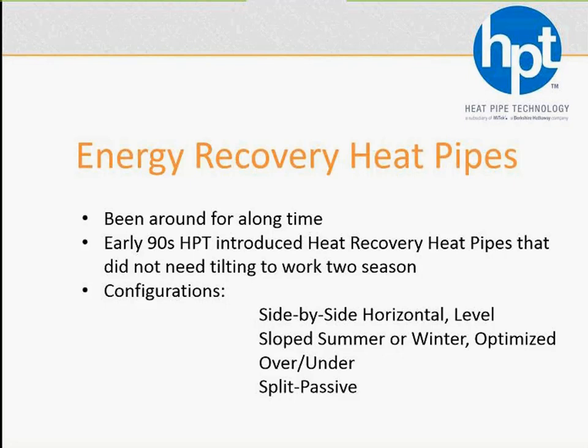Early 90s, HPT introduced heat recovery heat pipes that did not need tilting to operate, and still have this product, don't need to tilt it. However, as we said earlier, a little tilt goes a long way with heat pipes. Some of the products have that little tilt, permanent tilt, to enhance their performance in favor of a particular season. So, with this product, we have 4 configurations of design. At the popular side-by-side level, when you have equal summer-winter recovery, we have the permanent sloped for summer or winter, which we call optimized, our HRMZ product. We have the over-under airstreams, basically suitable for single-season recovery, and we have the split passive. And we'll talk about these separately in the coming slides.